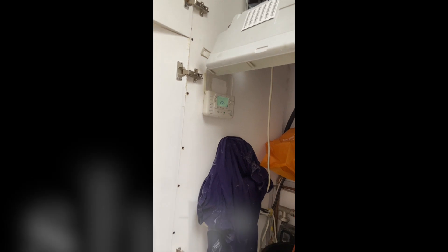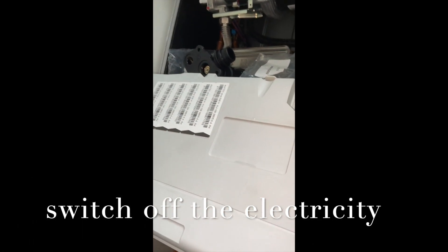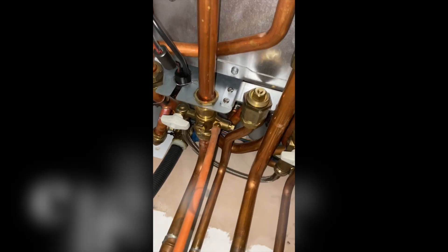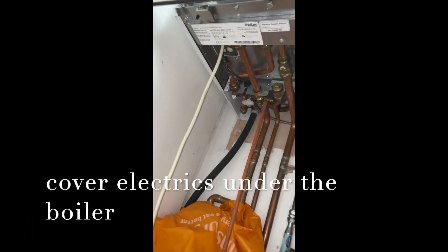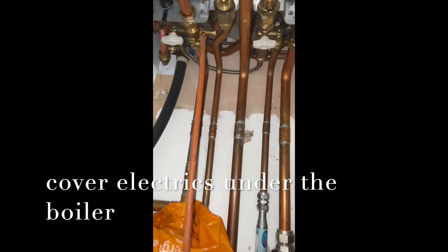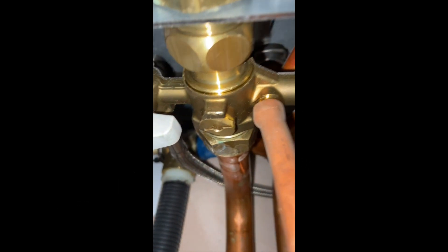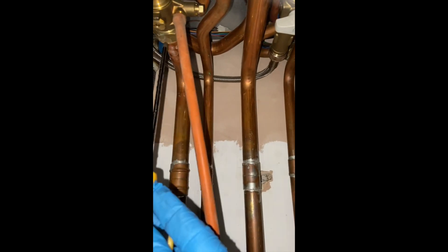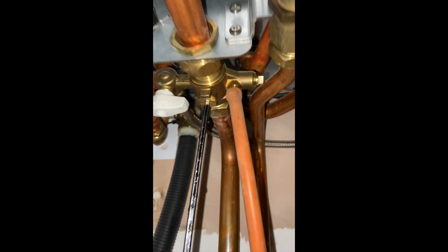Replace a diverter valve on an ecoTEC boiler. First, shut off the flow and return valves, which are these ones. That's the off position. I shut it off with an Allen key — I think it's 4 mil. So that's on the off position.